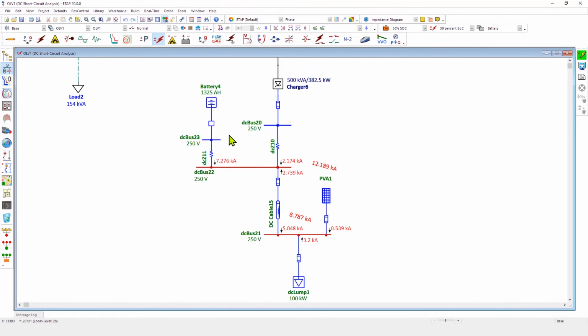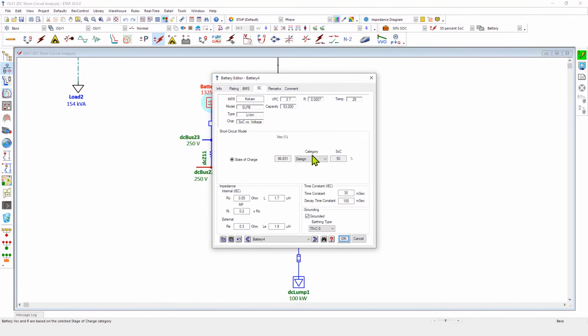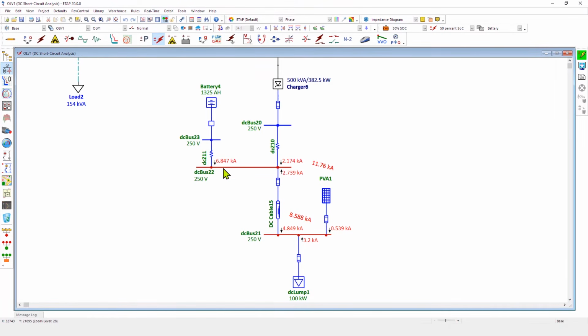And this is based on the battery model and the parametric model that we've previously defined. Similarly, if we go ahead and change our state of charge to a lower number, which is 25%, once again we can see our short circuit contribution is reduced. And based on this behavior, you can observe what would happen to the clearing times of protective devices. They would essentially tend to increase, increasing the I squared T and therefore the damage curve, particularly for DC arc flash cases. Therefore, the ability to model and simulate variable state of charge in DC short circuit is a very critical and important feature.